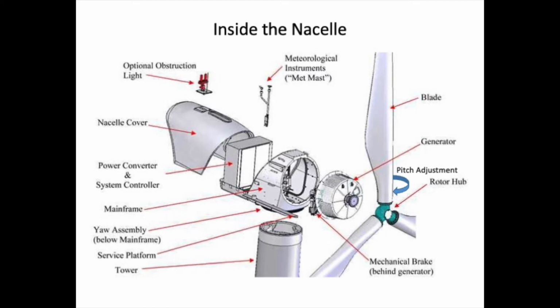The modern offshore wind turbines are direct drive. That means there's no gearing system to change the speed of rotation, but rather the generator is housed within this assembly right here. It's just a big drum. The inside of the drum remains fixed in space and has coils of wire. The outside rim of the drum rotates with the blades, and there are very powerful fixed magnets oriented like this.